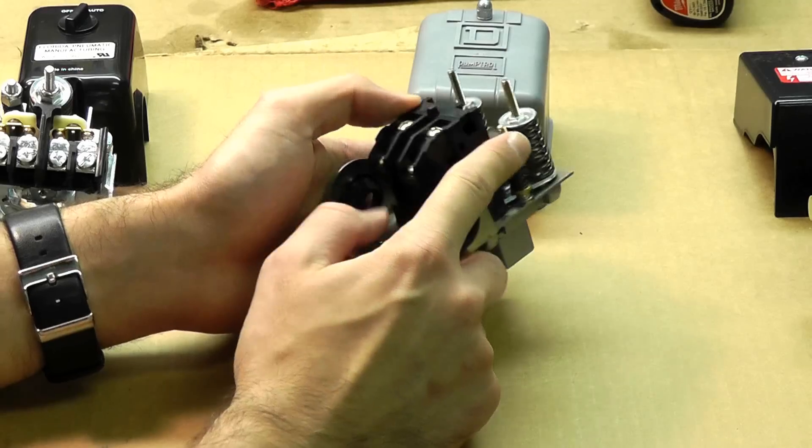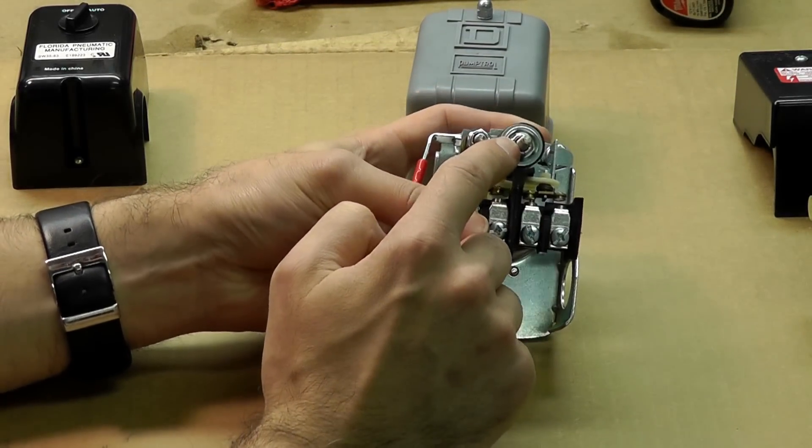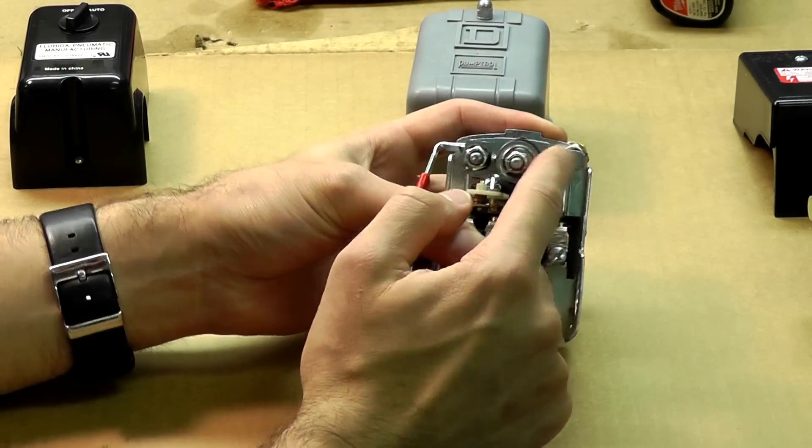And of course your Square D switch has a similar setup. It has the large screw which will adjust the main cut-in and cut-out pressure, or the minimum rather. So it's a minimum adjustment screw: clockwise to increase, counterclockwise to decrease.